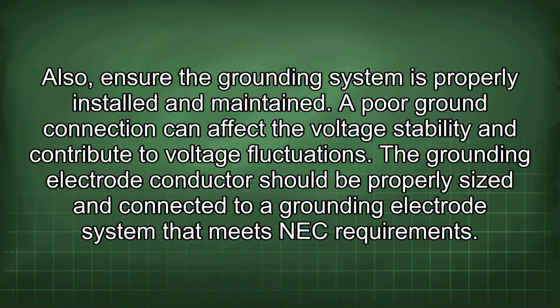Also, ensure the grounding system is properly installed and maintained. A poor ground connection can affect the voltage stability and contribute to voltage fluctuations. The grounding electrode conductor should be properly sized and connected to a grounding electrode system that meets NEC requirements.